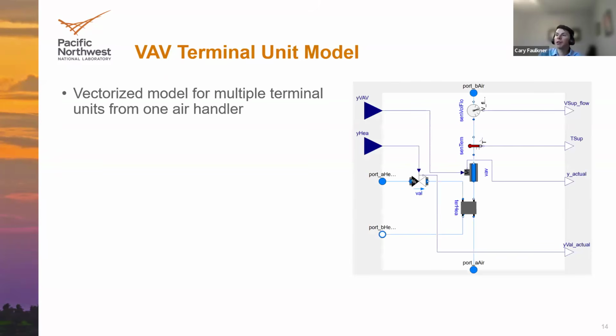Let's start here. I think the first aspect I want to mention is, the VAV systems are often used for an air handling unit that's serving multiple zones, and thus they might have multiple VAV boxes or terminal units for one air handling unit. And this model on the right here that I've opened up from the VAV system model shows one VAV terminal unit model, but it can be easily vectorized and then connected to the air handling unit model to show multiple similar VAV terminal units for one air handling unit, which is a convenient way to model these components in Modelica.